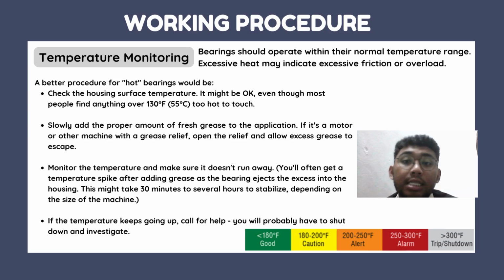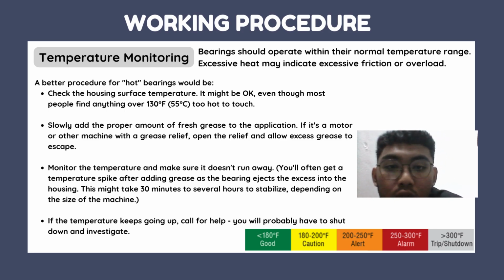Next one is about temperature monitoring. Bearings should operate within their normal temperature range. Excessive heat may indicate excessive friction or overload. A better procedure for a hot bearing would be to check the housing surface temperature. It might be okay, even though most people find anything over 130 Fahrenheit, which is 55 degrees Celsius, too hot to touch.